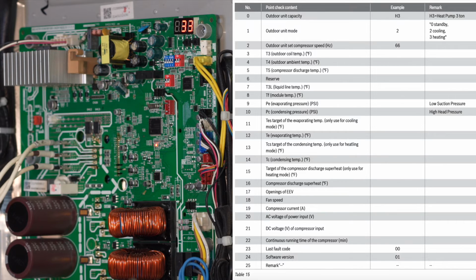The 22 was continuous run time. So at any time, if the unit is running and you scroll down to number 22, it's going to tell you in minutes how long that system has been running. Another little thing that I like about this: if you walk up to the unit and it is static or off, it's not running at all, it's satisfied, or it's not in either cooling or heating mode, if you go to number 22, it's not only continuous run time, but it will calculate the off time also. So remember, if the unit is static or off and you go to number 22, it's going to tell you how long that unit has been off.